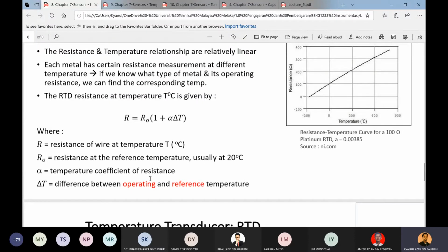The temperature coefficient depends on the material. For example, in this figure, a platinum RTD is used, and the alpha value here is 0.00385. So alpha always needs to be found based on the metal or material used.